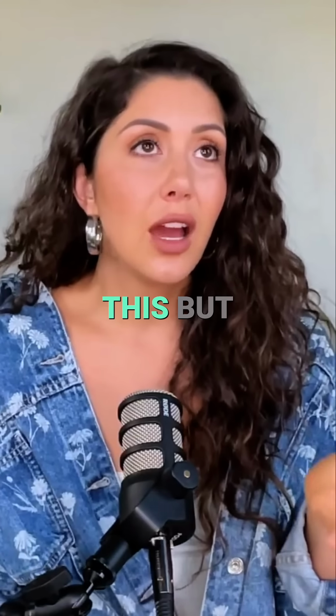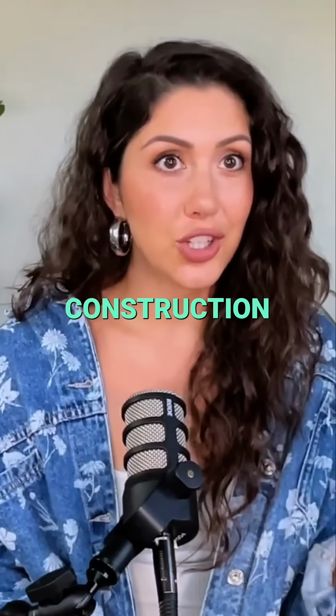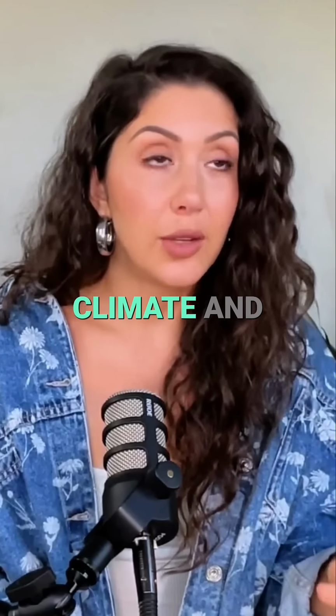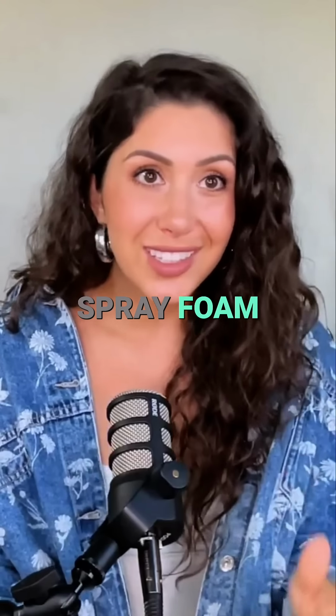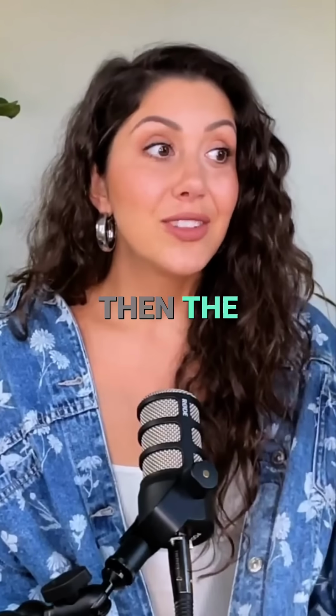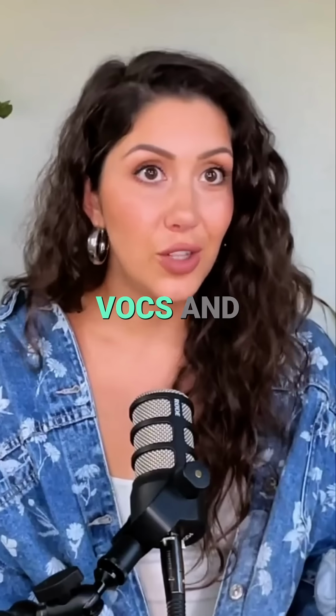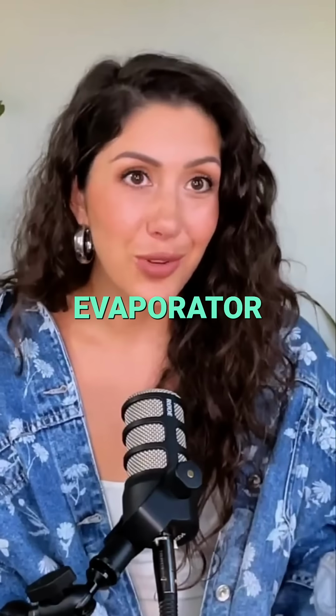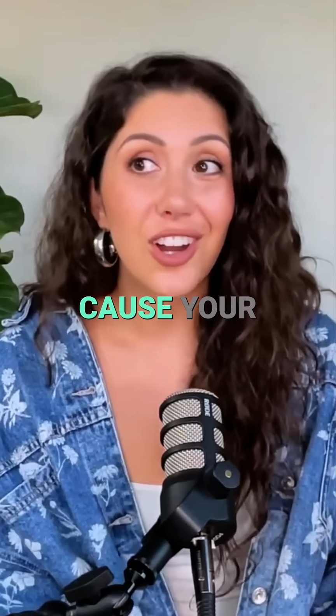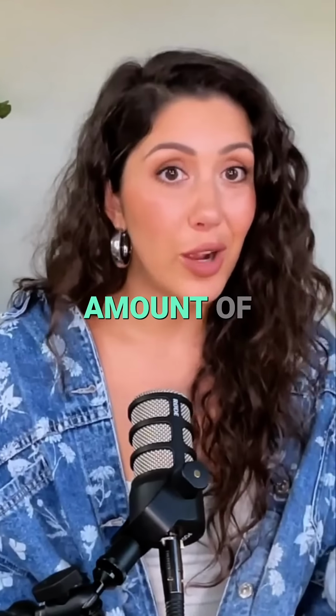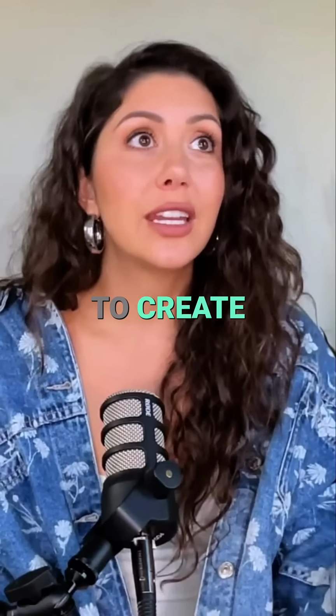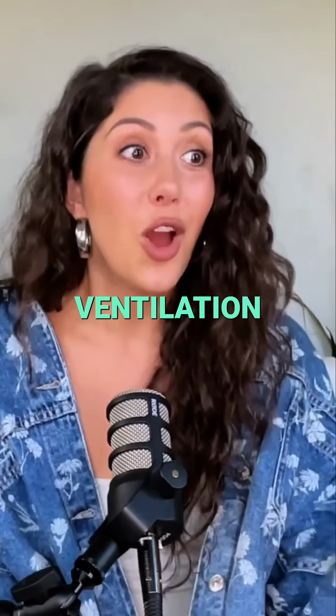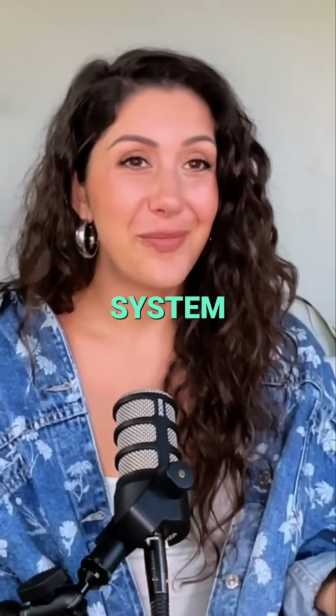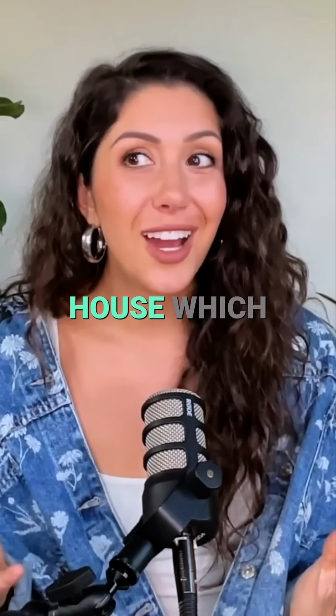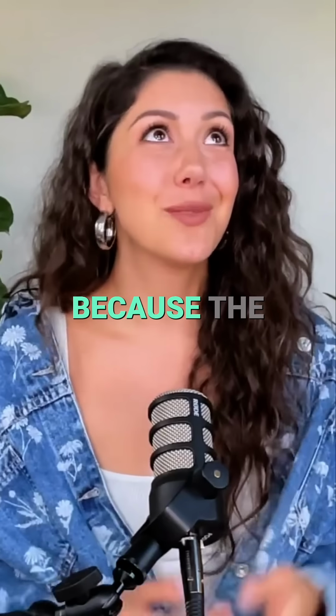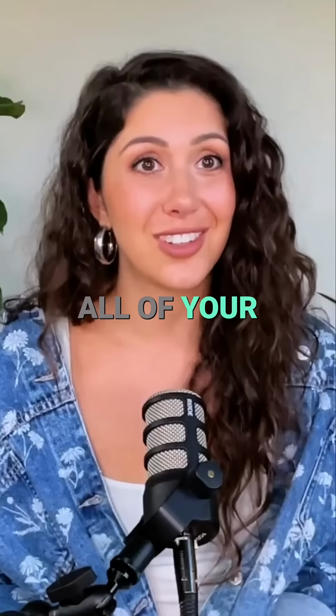You don't really need to understand all of this, but here's what you need to know: if you have new construction in Central Texas, or any hot and humid climate, and your HVAC system is in the attic surrounded by spray foam insulation, that new insulation will give off a ton of VOCs. Those VOCs degrade the evaporator coil and cause a Freon leak. The leak causes your HVAC system to work extra hard to produce the same amount of cool air, all while leaking fluid, which creates excess condensation in the attic. Since the attic has no ventilation, this creates mold in the HVAC system, which is connected to all the ductwork throughout your house. That means mold ends up in your entire house, because moldy air gets blown through all your ductwork and vents.